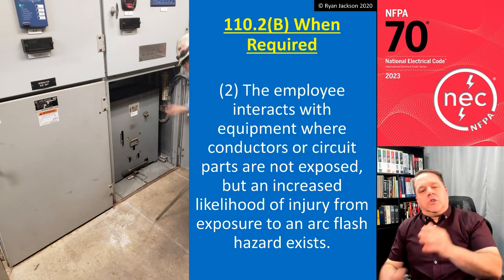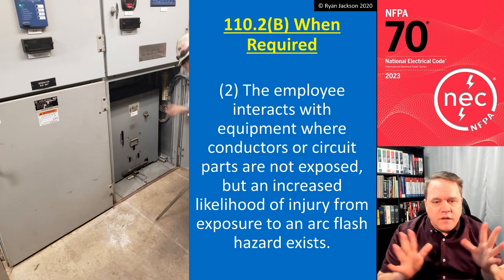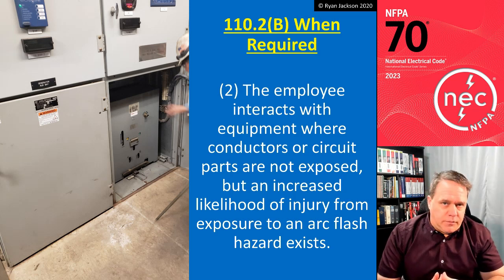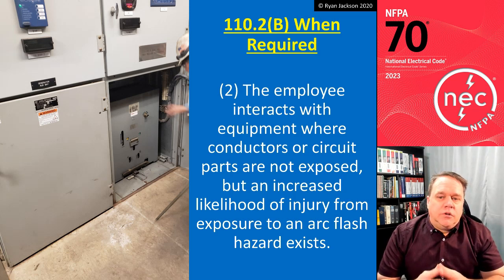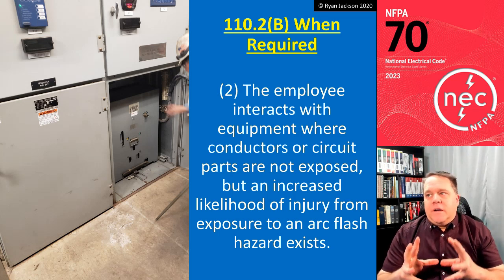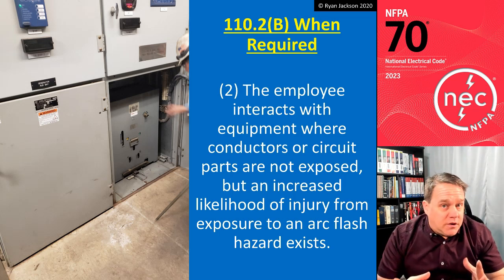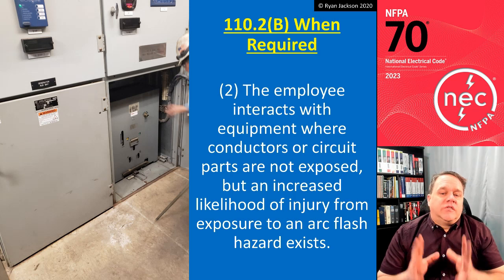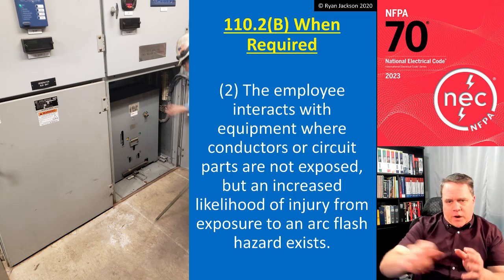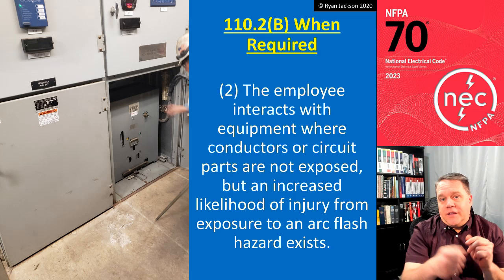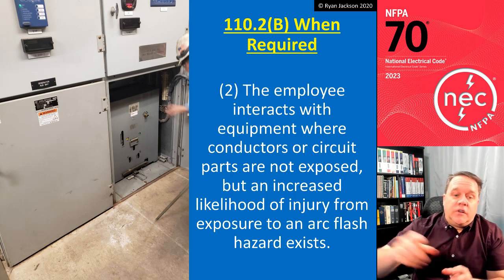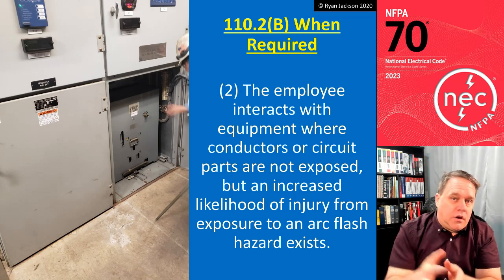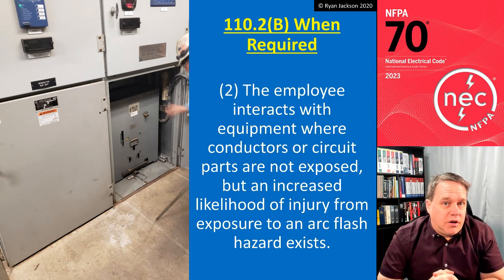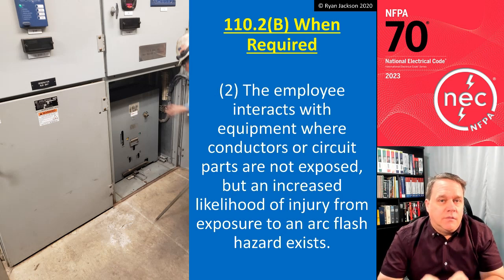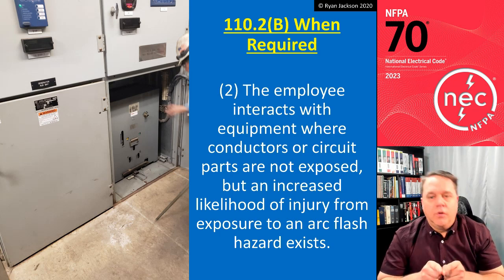Absolutely. What we're showing here in the picture is a rack-in style circuit breaker. And that absolutely is a piece of equipment or procedure that has an increased likelihood of injury. When I'm racking that circuit breaker in, if it's an energized piece of equipment, just the process of racking that thing in and making contact could potentially create an arc flash. So that thing needs to be shut off before I start racking breakers in or out. All right, so that's item 2.